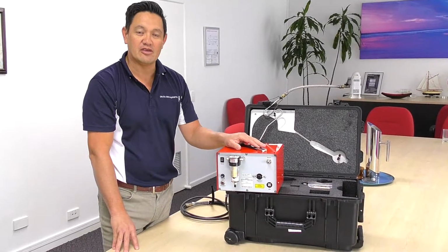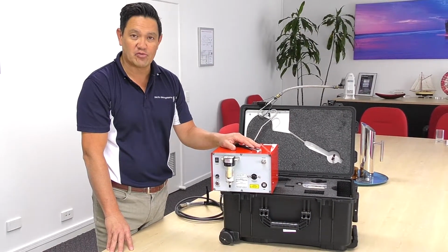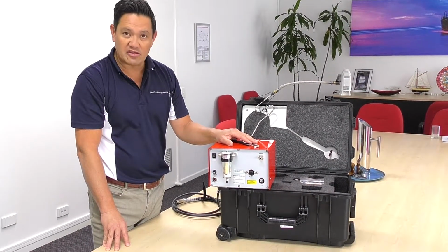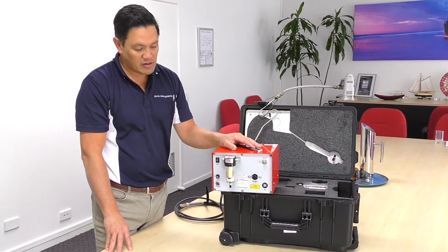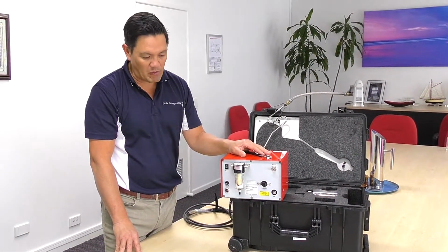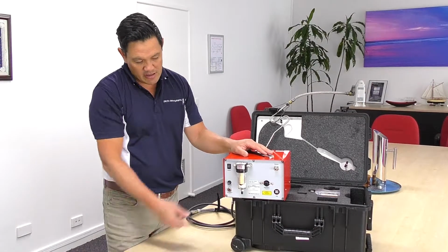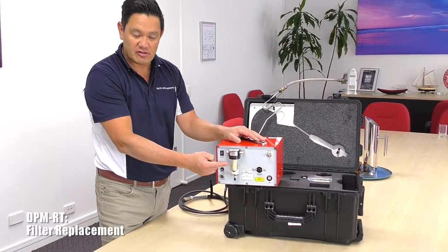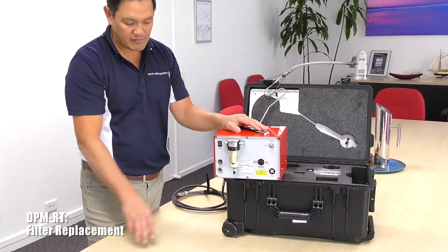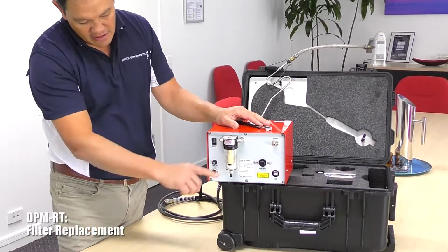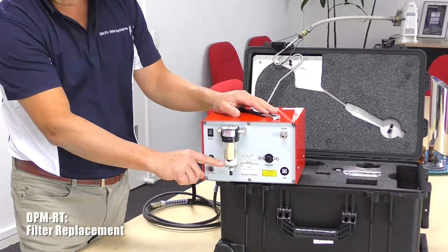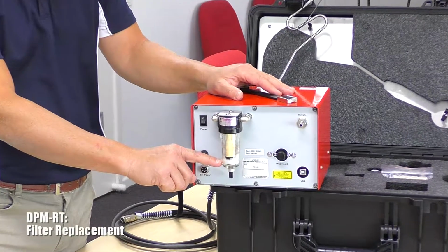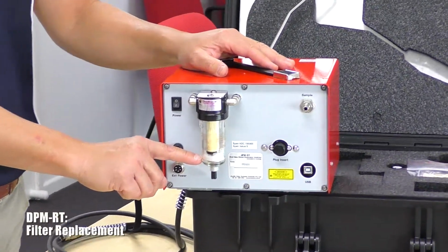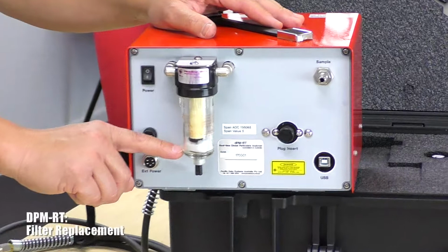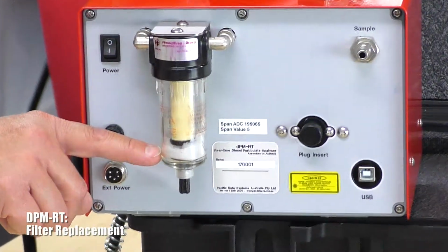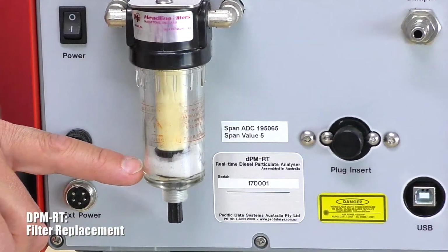The dPM-RT is a low maintenance field instrument. One of the things that you do need to ensure that you maintain for optimal performance is replacement of the filter. And you'll notice some material at the bottom of the filter chamber. That is to capture any moisture that has not been captured through the heating element in the sampling chamber.